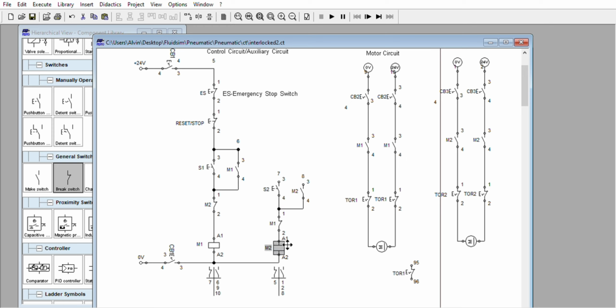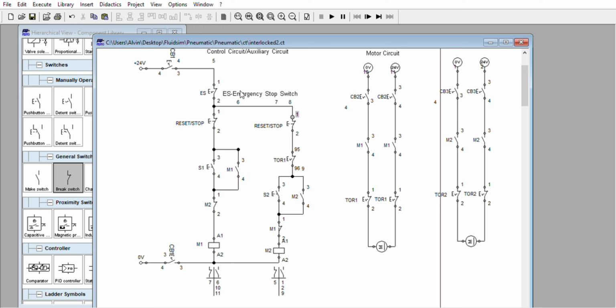Several times in European circuits that I troubleshoot, they have this connection. Overload relay is here. Okay, that is possible also. Dominant stop, that is always in series with the coil. And if you have another stop push button here, because you want a separate stop push button, you can have that one. And the emergency stop push button is common. You can have another emergency stop push button. It depends on your requirements.